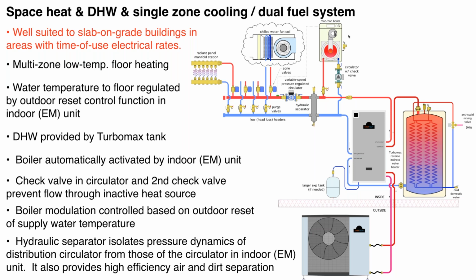And when that return water temperature to the conventional boiler drops below about 130 degrees, you will start to form flue gas condensation. And there are mixing valves that can easily be installed and protect that boiler. I just want to bring it up as a check mark. If you're retrofitting a system that does have a boiler that was not intended to operate with flue gas condensation, make sure you do that boiler protection. Now, I mentioned earlier, the controls that are in the indoor unit of the Enertech heat pump can automatically operate that auxiliary boiler.